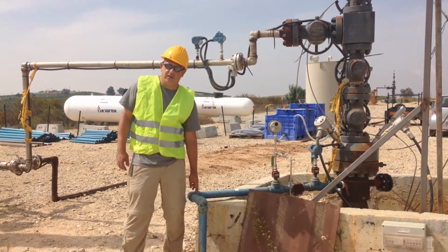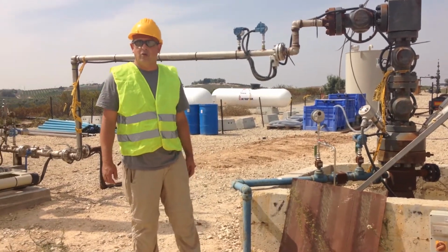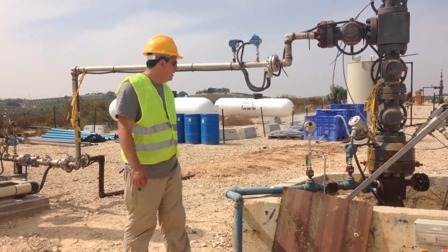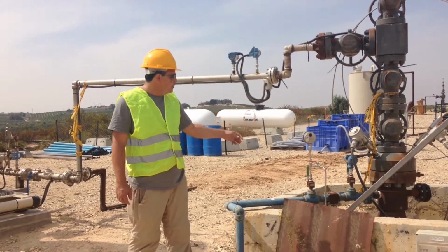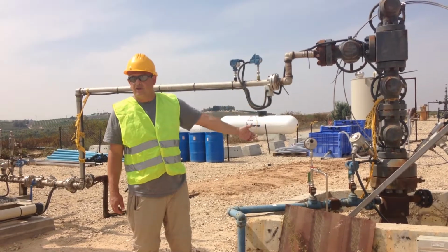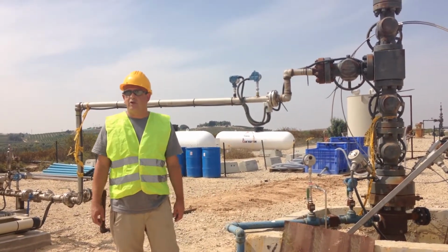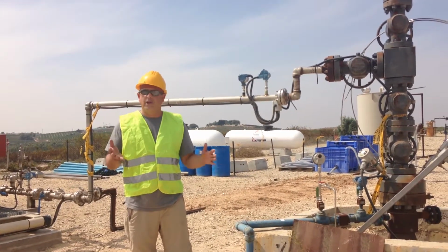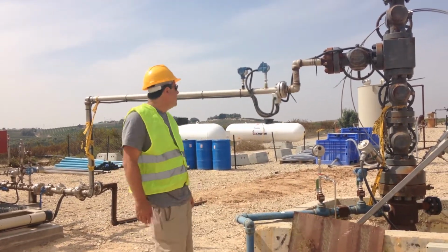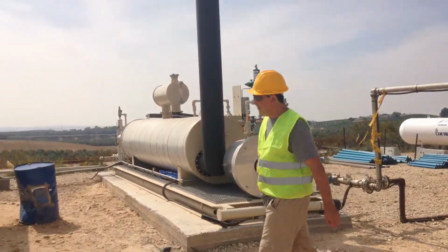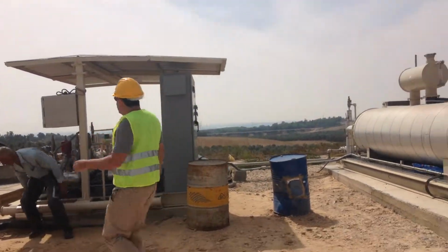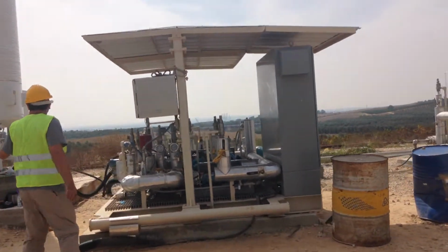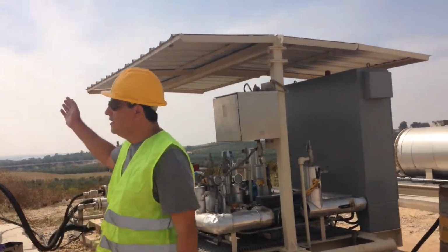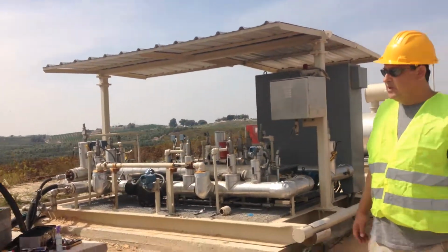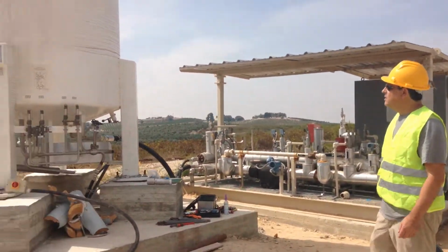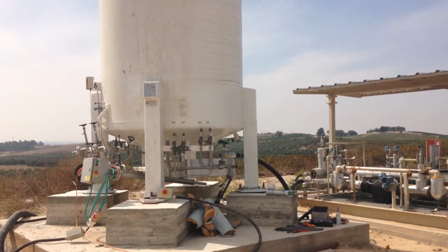That blue line here is a high pressure air line that allows water abstraction or fluid abstraction via airlift. We have pressure and temperature sensors in the critical path of the piping, so we have online, all the time, in the control room the complete information and control of what is going on. Now, what we have here is a CO2 tank, an installed CO2 tank with the capacity of 22 tons. It can deliver up to 4 tons per hour.